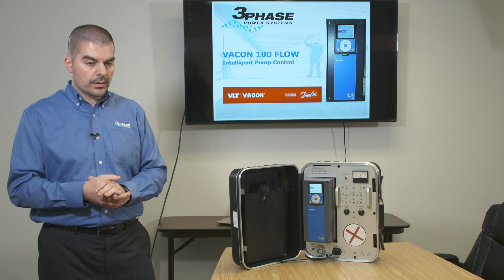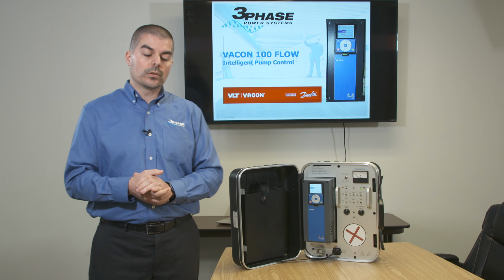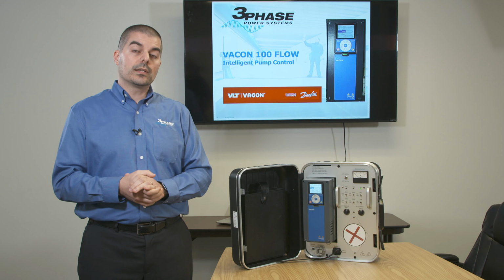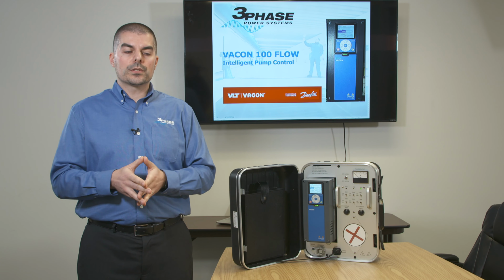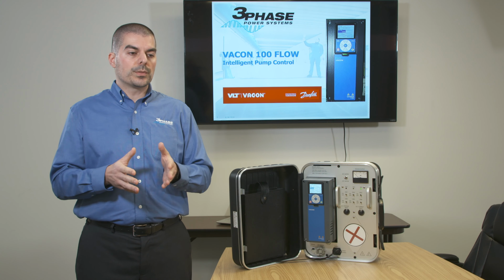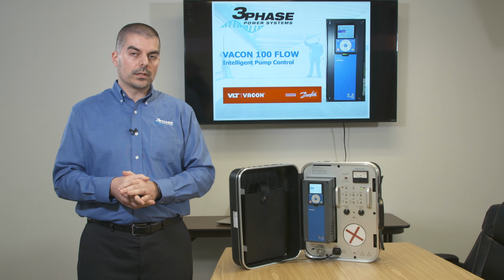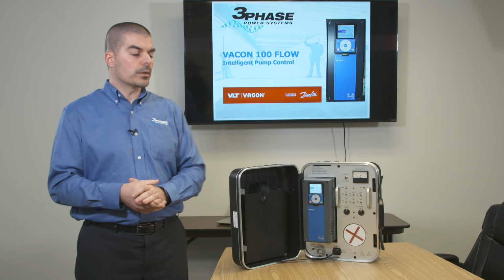The other fantastic thing about the VACON 100 Flow is the fact that it comes with an EMI RFI filter inside the drive, an EMC filter. Traditional drives, when they run, emit noise, and because of this noise there could be some potential 4 to 20 milliamp analog signal interference, which is inherently eliminated with the VACON 100 Flow.